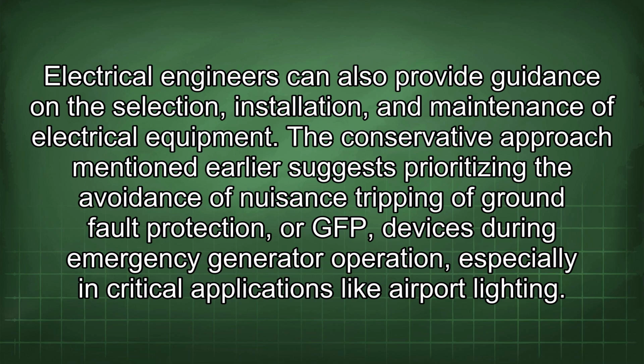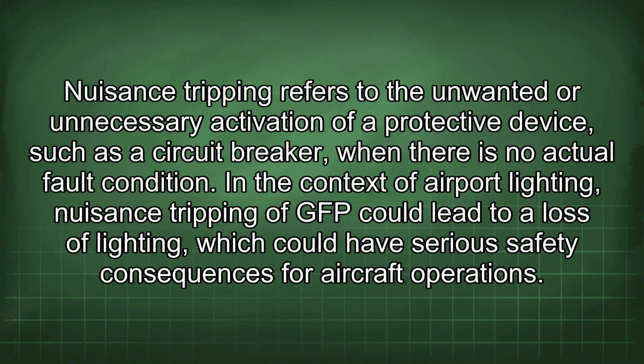The conservative approach mentioned earlier suggests prioritizing the avoidance of nuisance tripping of ground fault protection, or GFP, devices during emergency generator operation, especially in critical applications like airport lighting. Nuisance tripping refers to the unwanted or unnecessary activation of a protective device, such as a circuit breaker, when there is no actual fault condition. In the context of airport lighting, nuisance tripping of GFP could lead to a loss of lighting, which could have serious safety consequences for aircraft operations.